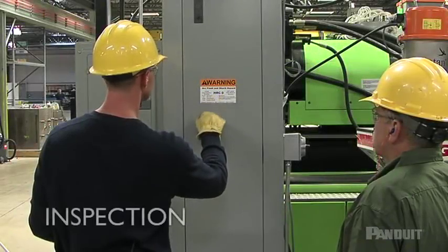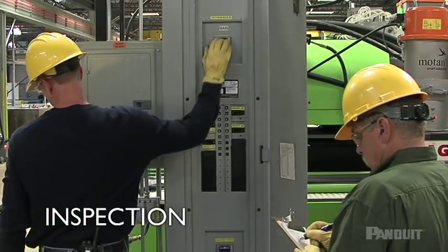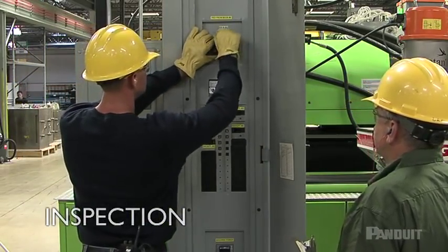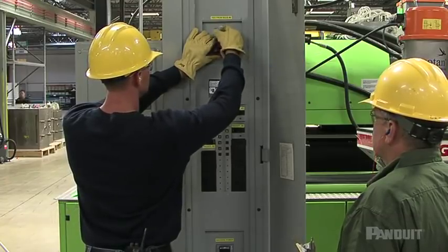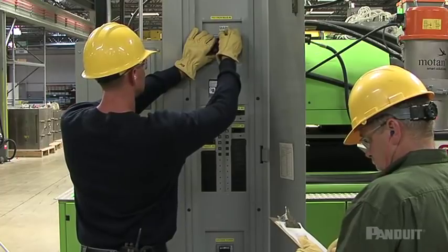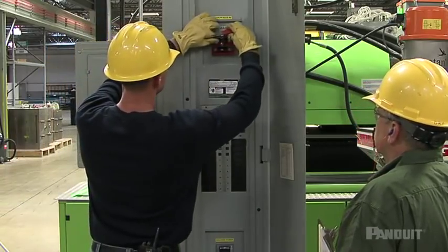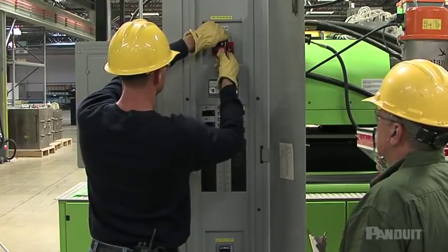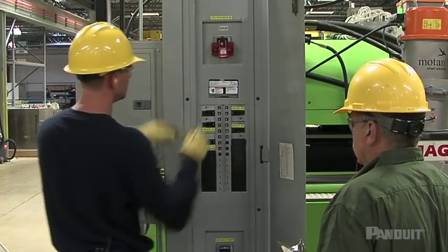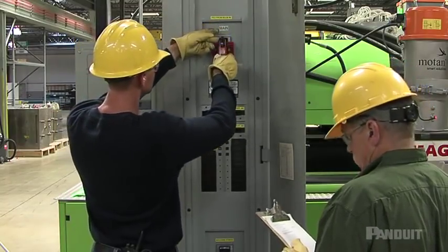Element 4: Inspection. Each employer must ensure personnel understand and comply with all relevant and applicable energy control program regulations. Periodic inspection of each lockout-tagout procedure must be performed at least once a year by an authorized employee other than the one utilizing the energy control procedure under inspection. These inspections are designed to ensure that energy control procedures are still adequate, continue to be properly implemented, and that employees are familiar with their responsibilities.